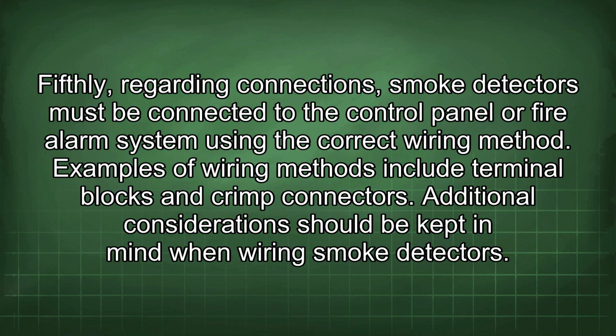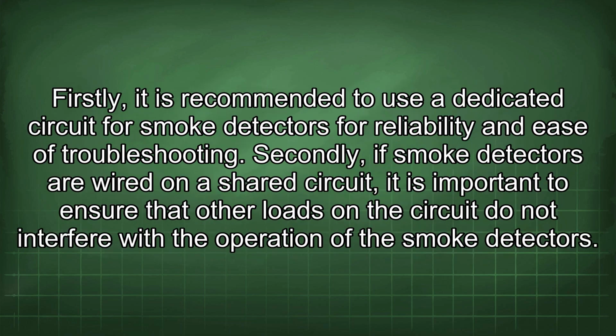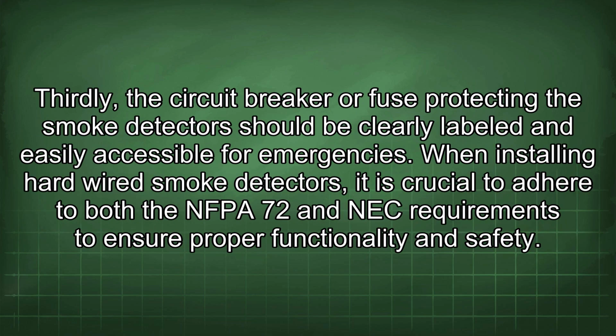Additional considerations should be kept in mind when wiring smoke detectors. Firstly, it is recommended to use a dedicated circuit for smoke detectors for reliability and ease of troubleshooting. Secondly, if smoke detectors are wired on a shared circuit, it is important to ensure that other loads on the circuit do not interfere with the operation of the smoke detectors. Thirdly, the circuit breaker or fuse protecting the smoke detectors should be clearly labeled and easily accessible for emergencies.